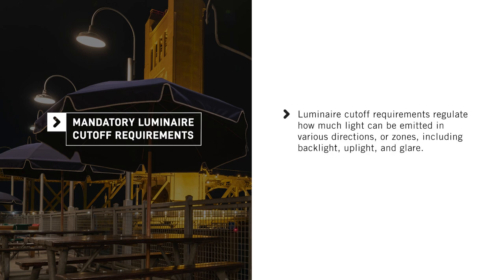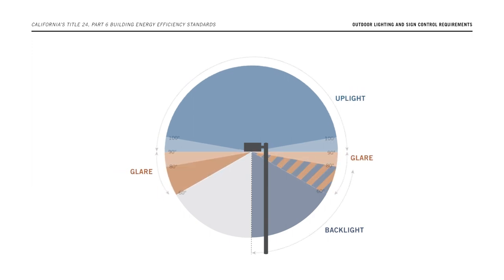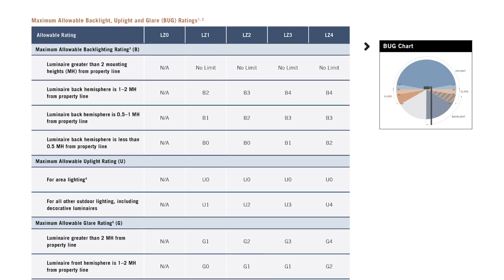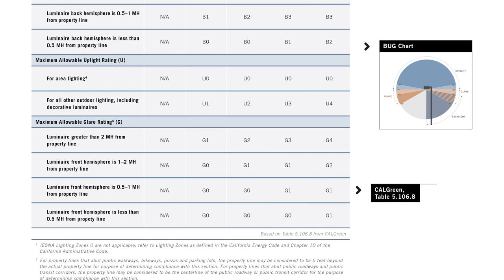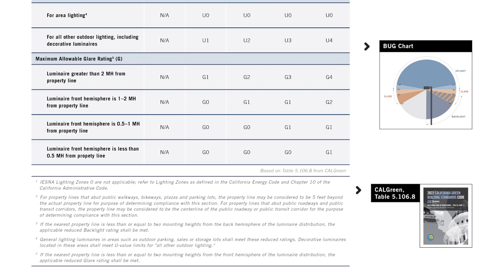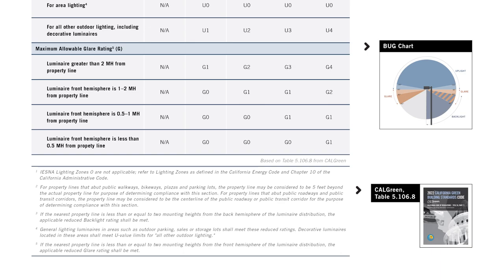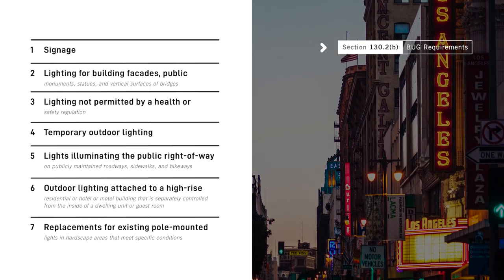Now let's talk about the mandatory requirements pertaining to luminaire cutoff and the exceptions. Luminaire cutoff requirements regulate how much light can be emitted in various directions or zones, including backlight, uplight, and glare. Many types of outdoor lights must comply with these cutoff requirements, which are collectively referred to as BUG requirements. The Energy Code's BUG requirements specify maximum zonal lumens and only apply to outdoor lights rated 6200 initial lumens or more. Specific requirements are provided in Title 24, Part 11, Section 5.106.8, also referred to as the CalGreen Code. Seven types of outdoor lighting need not comply with the BUG requirements; illuminated outdoor signs are one such example.